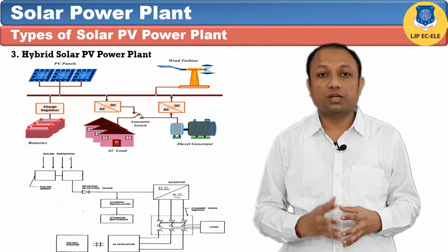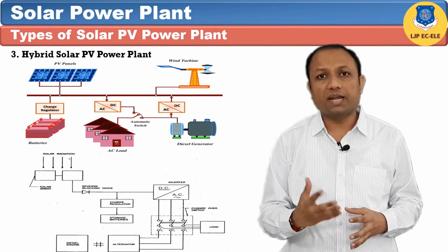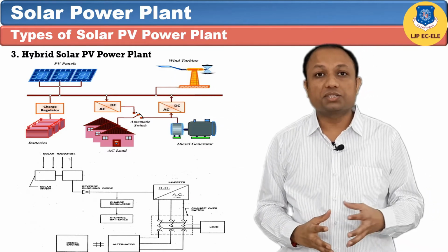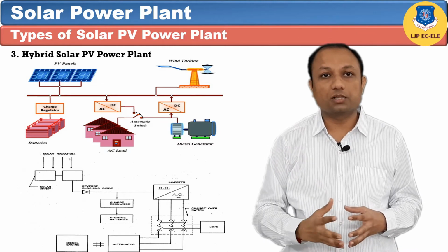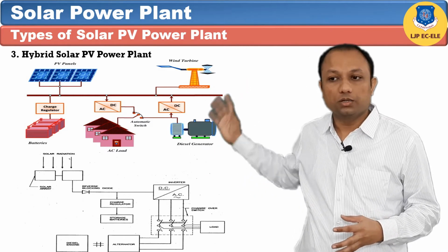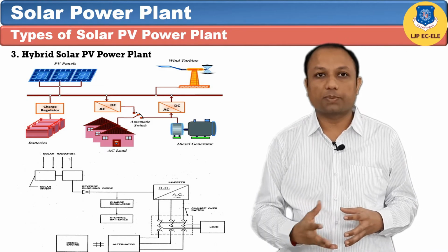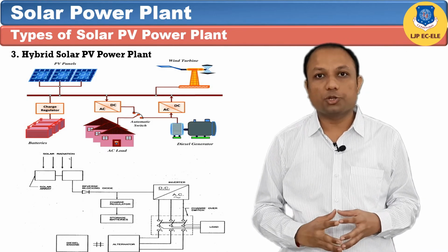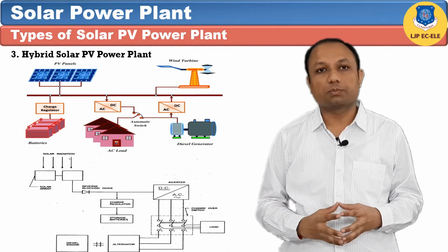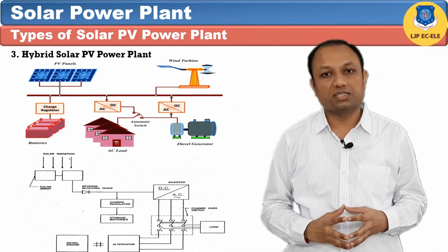Solar energy is converted into electrical energy by the solar PV system during the daytime. The batteries are charged through the reverse blocking diode and the charge regulating circuit. DC is converted into three-phase or single-phase AC with the help of inverters. AC is fed to the load. During the absence of the sunlight, the system continues the power supply, but when the capacity of the battery to supply power reduces, the diesel generator is run and the power supply is continued. Use of batteries can be omitted as the diesel set is used.